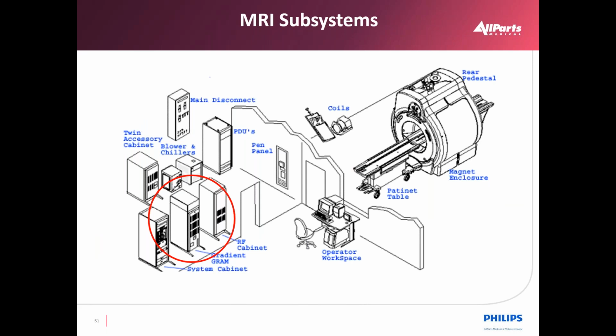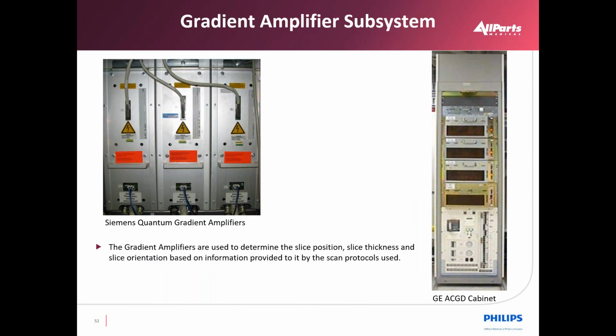The gradient section contains 3 gradient amplifiers used to produce calibrated magnetic field changes based on digital input in the X, Y, and Z coordinates. Gradient amplifiers are high current devices used to determine the slice position, thickness, and orientation based off the scan protocols used.